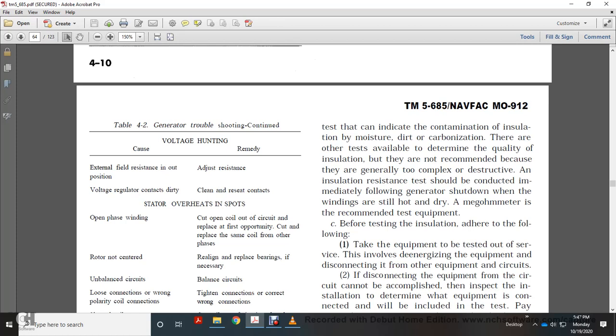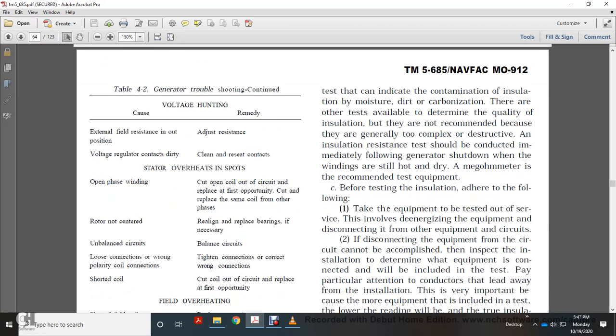Adhere to the following: take the equipment to be tested out of service. This involves de-energizing the equipment and disconnecting the equipment circuit. If the circuit cannot be disconnected, the insulation test must determine which equipment it is connected with, to be included in the test.